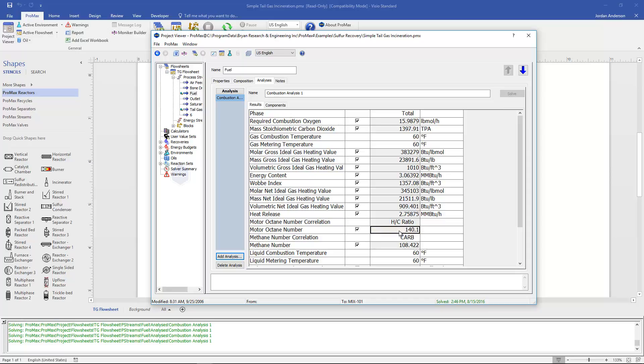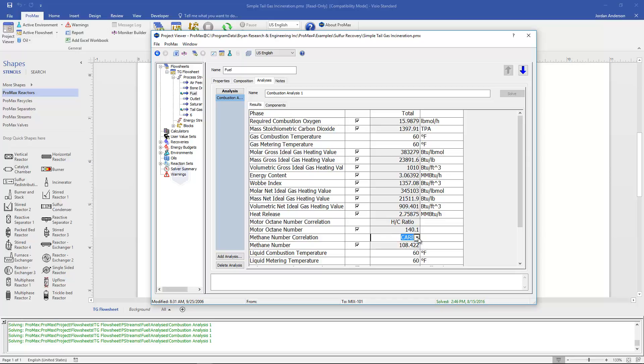Now this octane number is different than what you would normally think about with liquid fuels. This motor octane number is for natural gas as is the methane number. But those can be calculated and the methane number correlations are these two different options that we have to choose from.